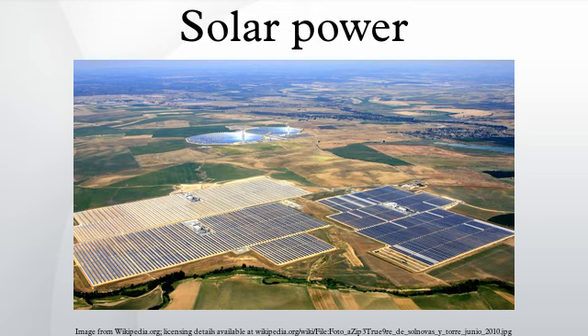A parabolic trough consists of a linear parabolic reflector that concentrates light onto a receiver positioned along the reflector's focal line. The receiver is a tube positioned right above the middle of the parabolic mirror and is filled with a working fluid. The reflector is made to follow the sun during daylight hours by tracking along a single axis. Parabolic trough systems provide the best land use factor of any solar technology. The SEGS plants in California and Acciona's Nevada Solar One near Boulder City, Nevada are representatives of this technology.